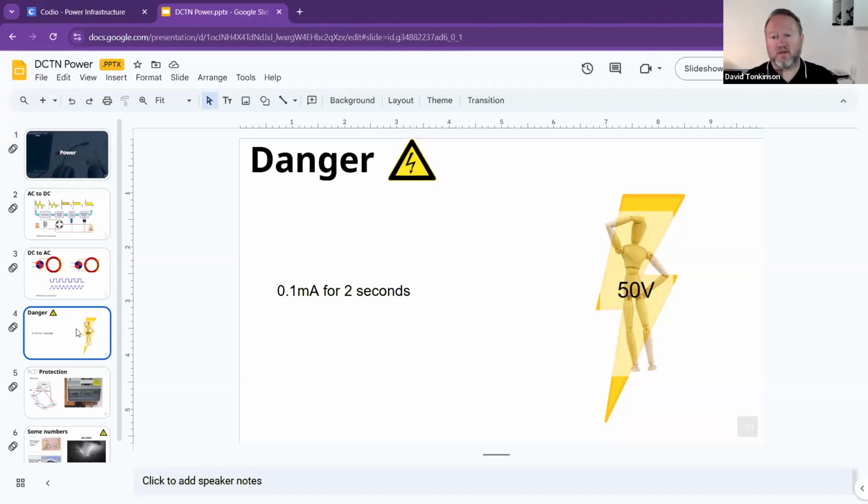For mission critical things, such as power generator tests, when you're doing full tests and things like that, you normally qualify the person to do that full generator test, but you would then make sure that someone goes with him. So you buddy up. When you're doing anything mission critical, buddy up. There's two of you there. One of you looks blankly at the other one and goes, I'm not sure what we're doing. Then you both go back to the operations manual and double check it. Okay, and it only takes one of you to be slightly hesitant that you both go back and check it. So it's always better to be safe than to drop someone's system. Does that make sense for you, Kadir?